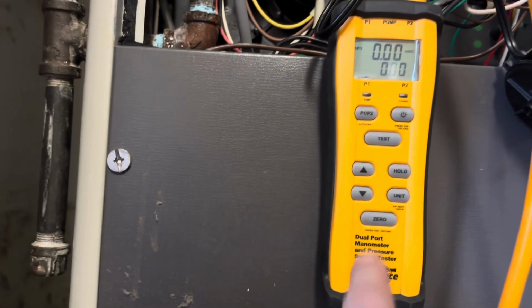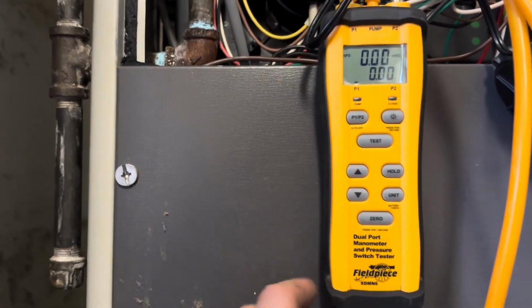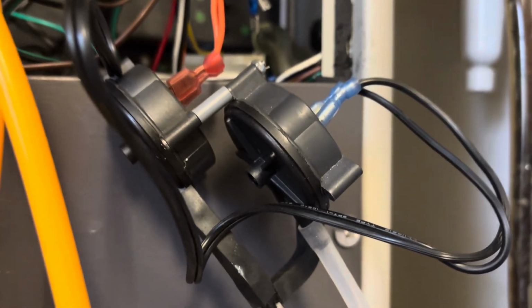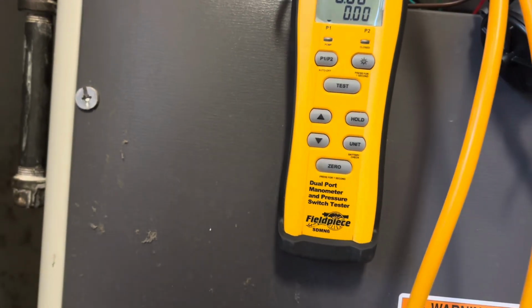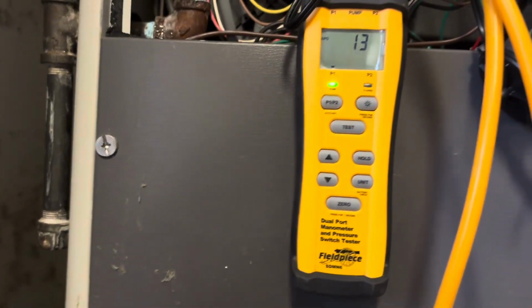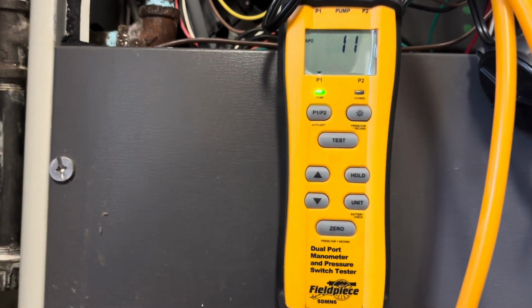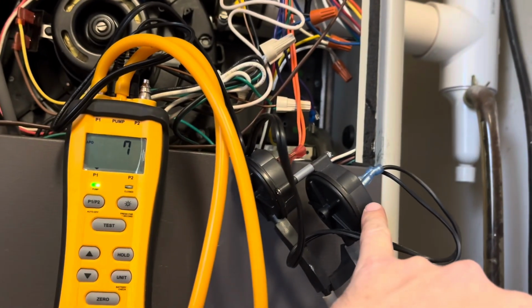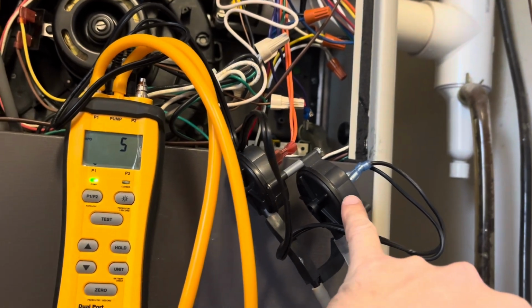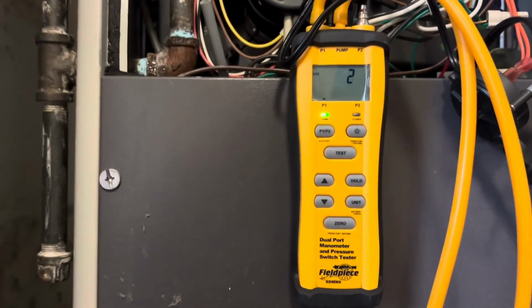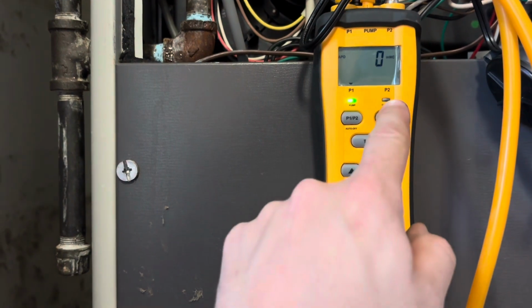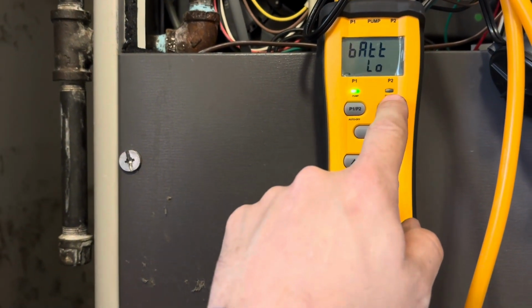All right guys, we're using an option on this dual port manometer that I don't use very often, but it's the pressure switch tester. This is a 1.0 switch, so we're gonna test it now and see exactly what it's at. Basically our meter is going to apply pressure in small increments to our pressure switch until it closes. Once it closes, this little red light will come up. You see it was closed.